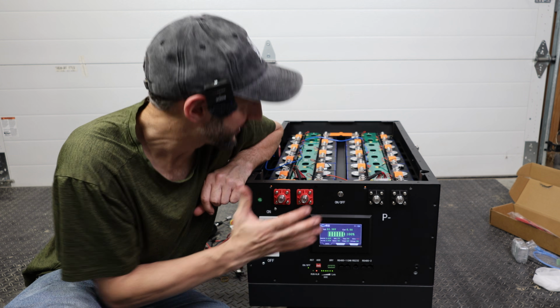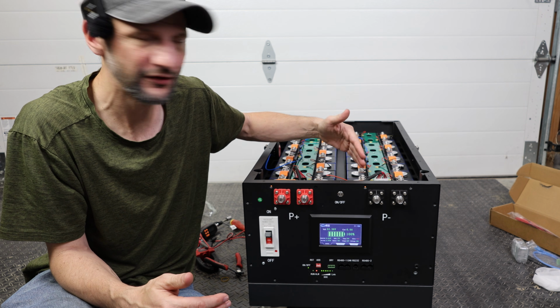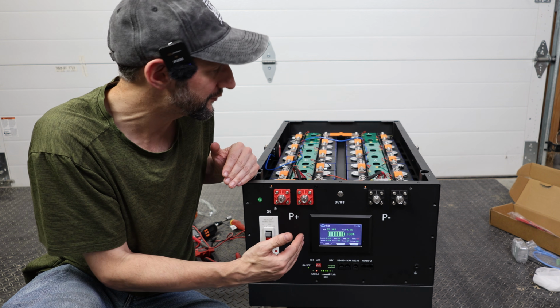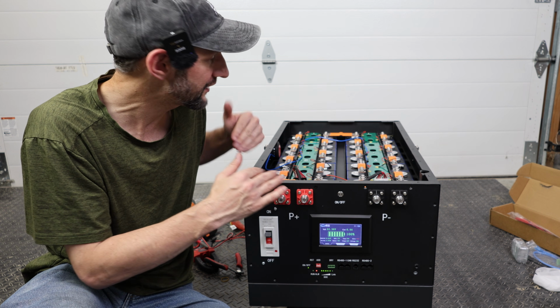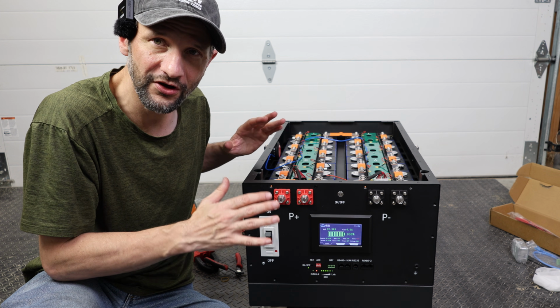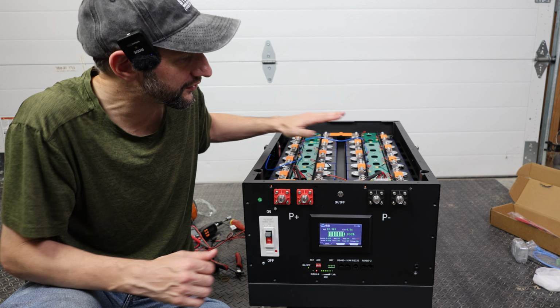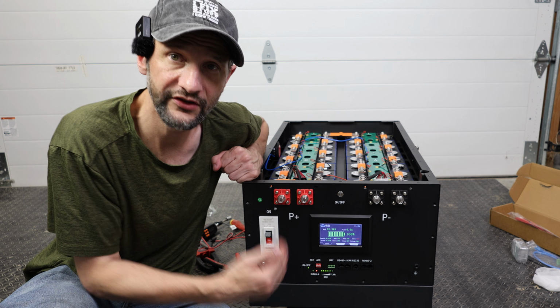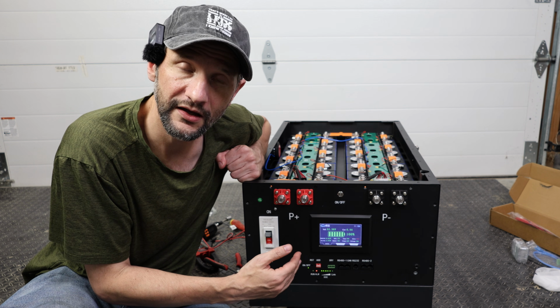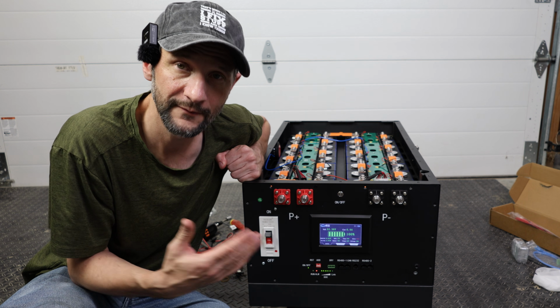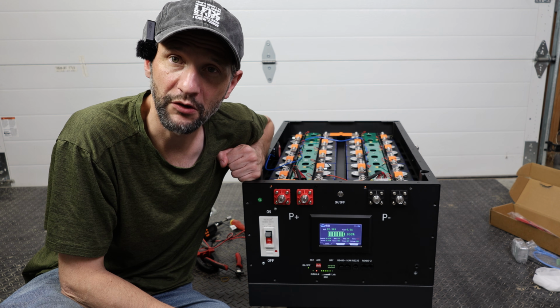Everything's functioning. We have over 52 volts across the main terminals, the BMS power is on, and we've checked the torque for everything. The fire suppressor is installed, and everything's good to go. So I'll put the lid on, fasten the rest of the screws, and then go through the BMS settings to get it set up.